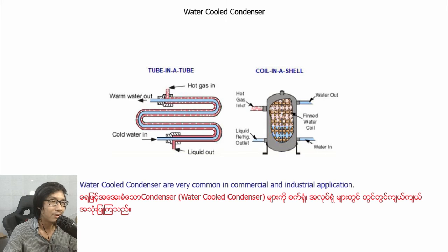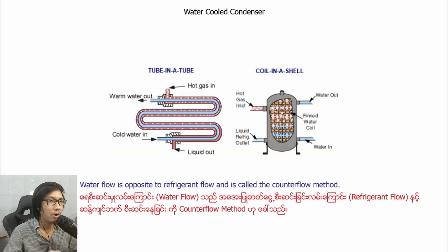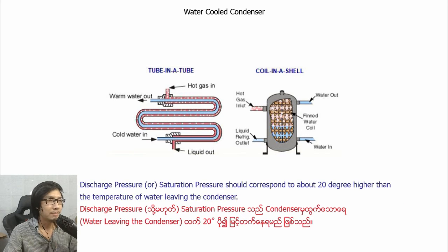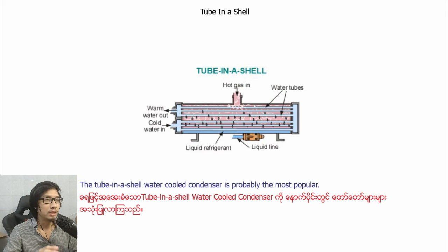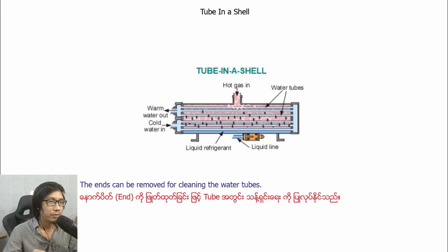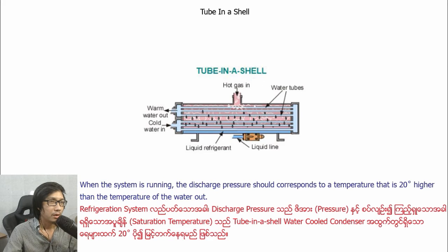Water-cooled condenser. Water-cooled condensers are very common in commercial and industrial applications. Water flow is opposite to the refrigerant flow and is called the counterflow method. Discharge pressure or saturation pressure should correspond to about 20 degrees higher than the temperature of water leaving the condenser. The tube-in-a-shell water-cooled condenser is probably the most popular. The end can be removed for cleaning the water tubes. When the system is running, the discharge pressure should correspond to a temperature that is 20 degrees higher than the temperature of the water outlet.